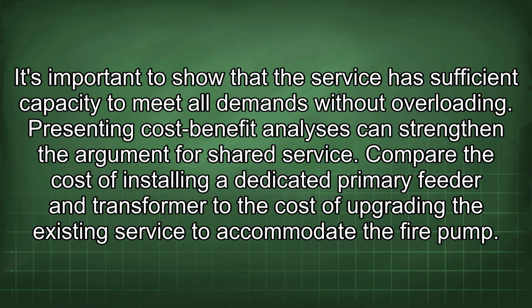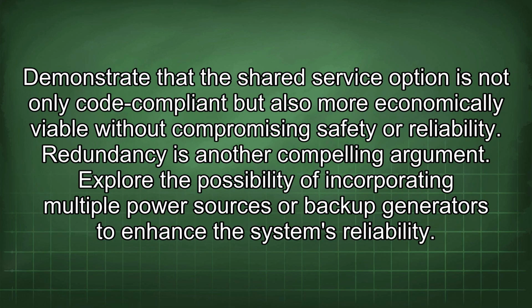Presenting cost-benefit analyses can strengthen the argument for shared service. Compare the cost of installing a dedicated primary feeder and transformer to the cost of upgrading the existing service to accommodate the fire pump. Demonstrate that the shared service option is not only code compliant but also more economically viable without compromising safety or reliability.